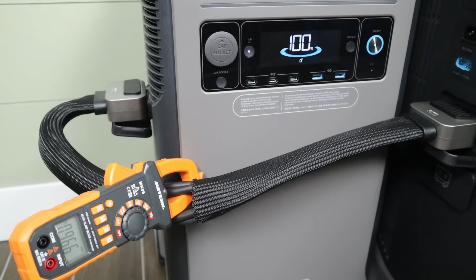So I've started the test. I have two 500 watt heaters running off the 240 volt output, each running off a leg of 120—that's what that adapter does. Looking at the screen, we have 942 watts going out of the power station. I want to get a clamp meter and see how much power is going through this cable.